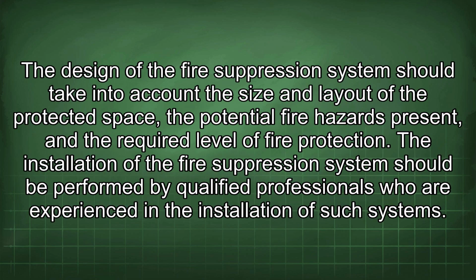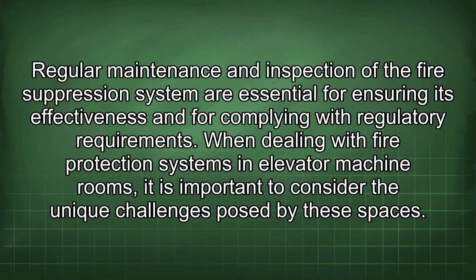The design of the fire suppression system should take into account the size and layout of the protected space, the potential fire hazards present, and the required level of fire protection. The installation of the fire suppression system should be performed by qualified professionals who are experienced in the installation of such systems. Regular maintenance and inspection of the fire suppression system are essential for ensuring its effectiveness and for complying with regulatory requirements. When dealing with fire protection systems in elevator machine rooms, it is important to consider the unique challenges posed by these spaces.